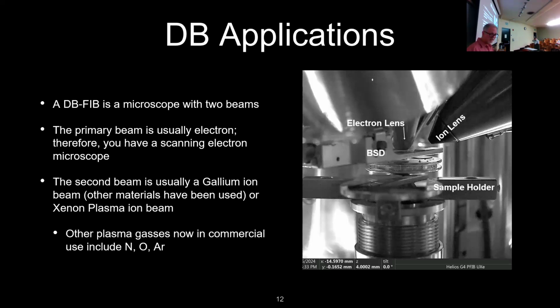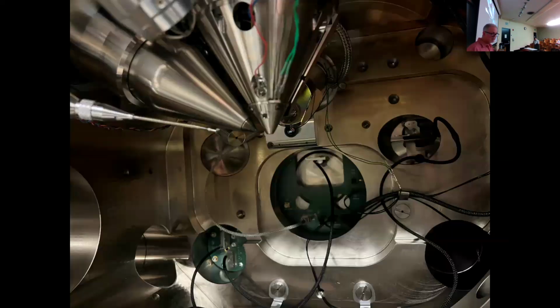And this is one of many sample holders we have for the microscope. This is a front view. That camera is in the back of the microscope looking forward, and this is a little bit out of focus. I'd say I'm sorry about that, but the reason I took this picture is I was trying to look at the electron scintillator screen as we were putting this back together, to see what condition it was in. I could get a good enough view from this to know it needed to be replaced. It had maybe 1,000 hours on that screen. It's a $2,000 part. And that's the actual chamber cam from the previous view.